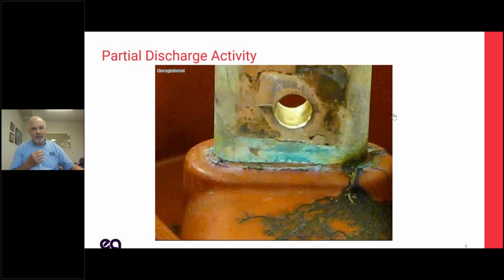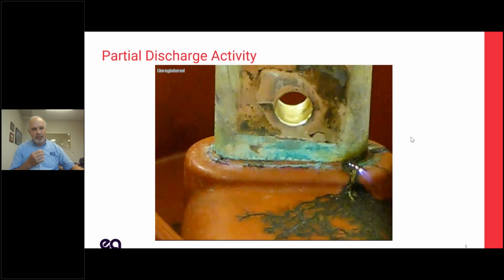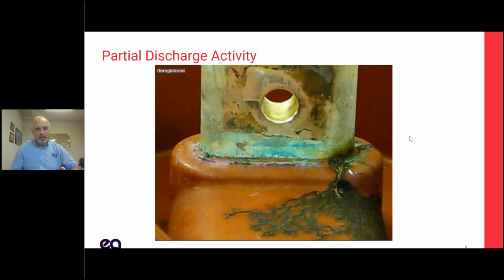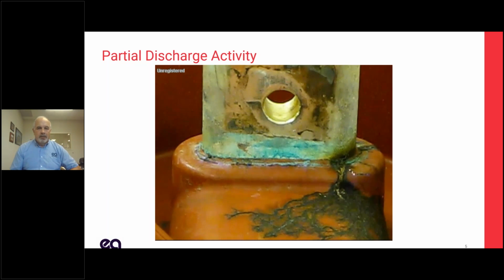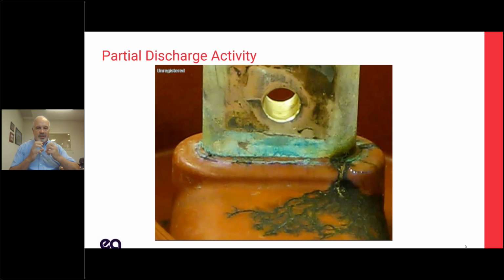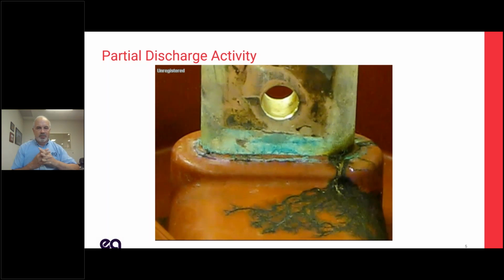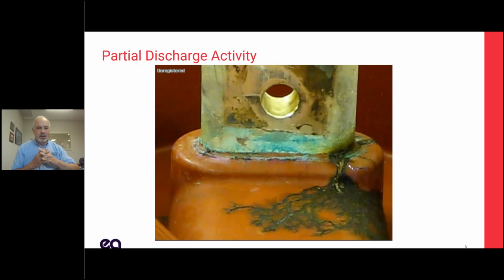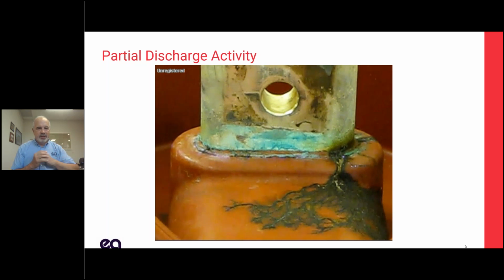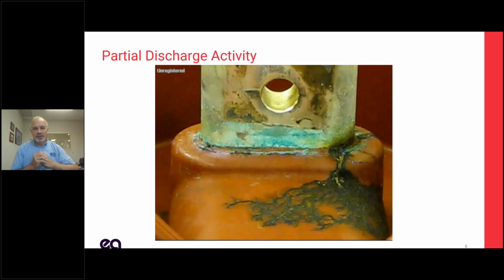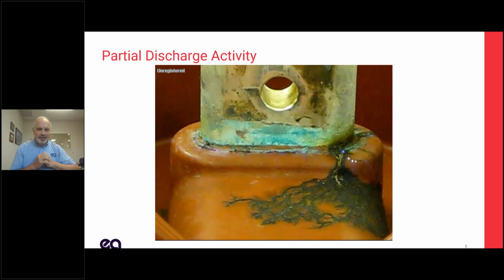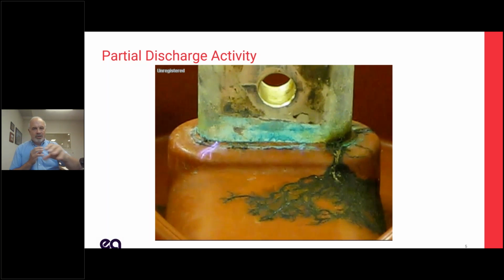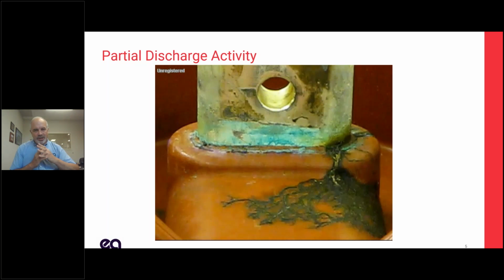We have a little video here. Hopefully that'll play. You can see these little flashovers. On the right side, it's a little more consistent, and then on the left side you see it arcing over. This is classic partial discharge. Don't let anyone tell you it doesn't exist. That black tracking on the insulator is characteristic of what you'll find after a long period of partial discharge.